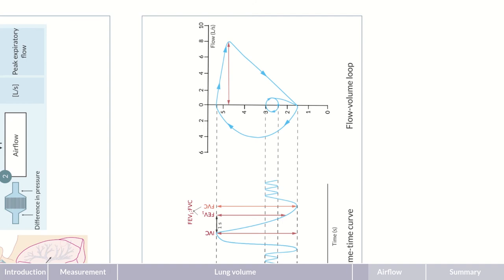In addition to the peak expiratory flow, there's also the mean expiratory flow. With these parameters, the curve can be specified at certain time points in which a particular percentage of the vital capacity has been exhaled. So, the parameters are measured at 25%, 50%, and 75% of the forced vital capacity. These values are usually abbreviated as FEF, for forced expiratory flow, followed by the percentage, which are FEF 25%, FEF 50%, and FEF 75%.